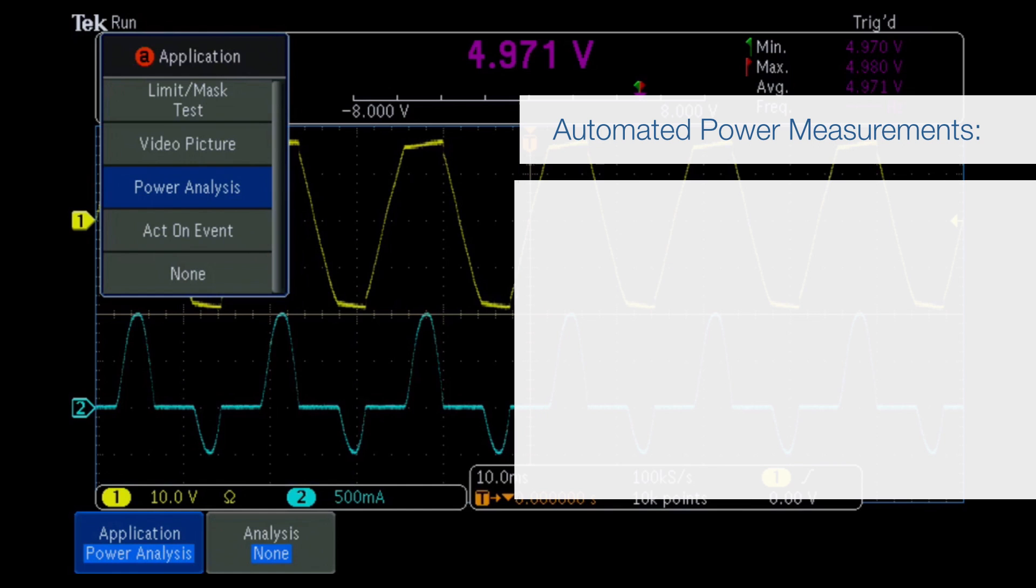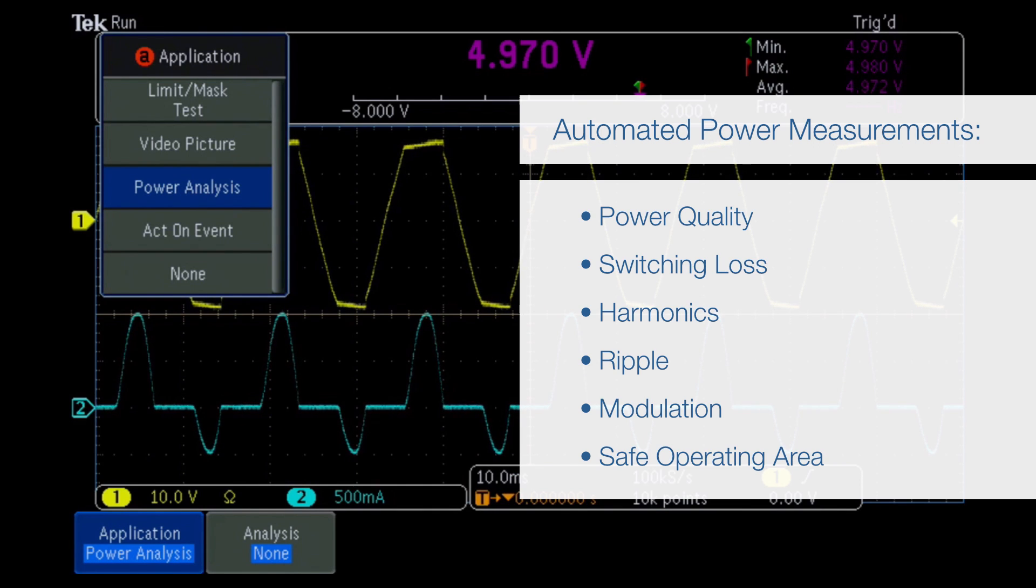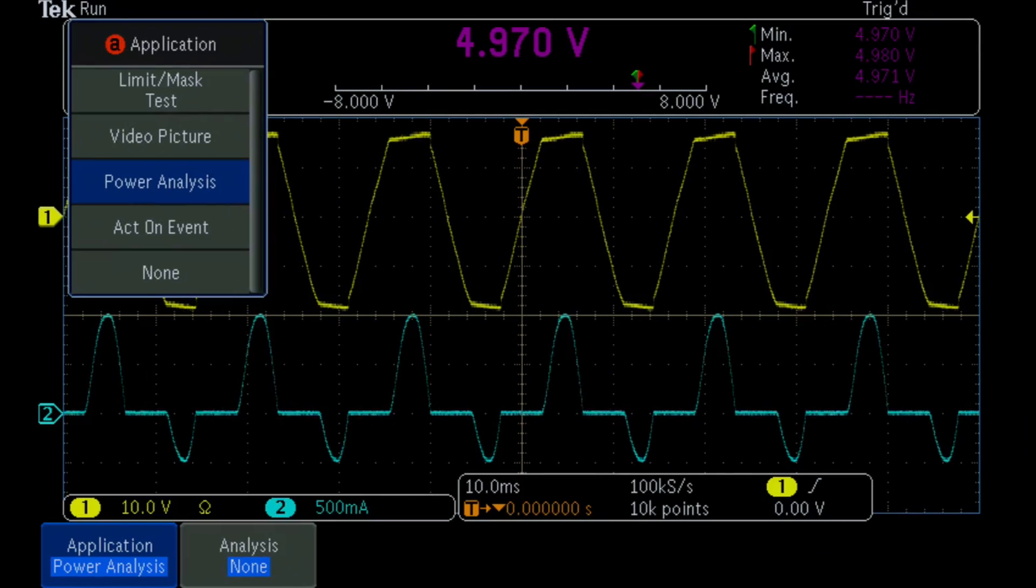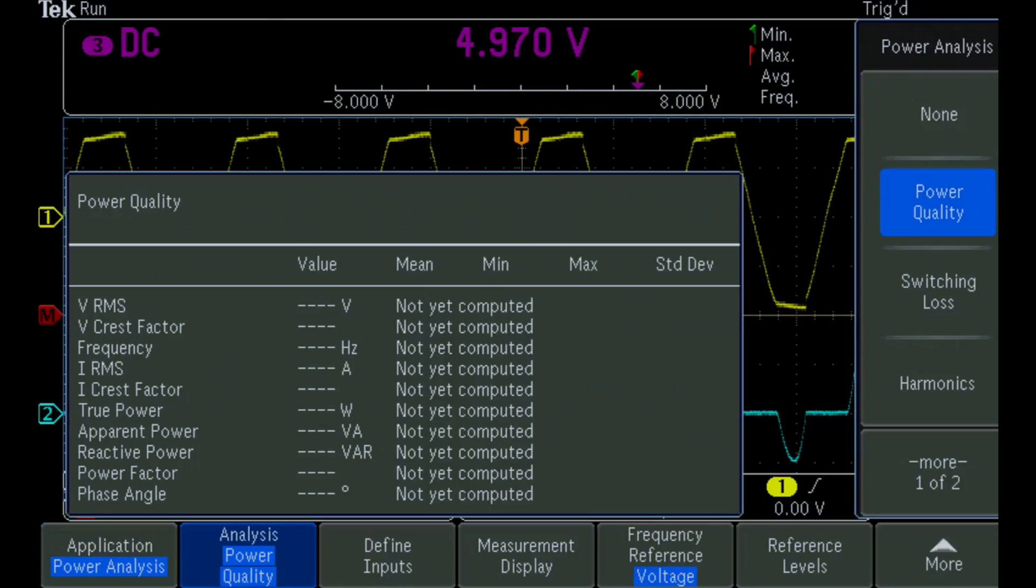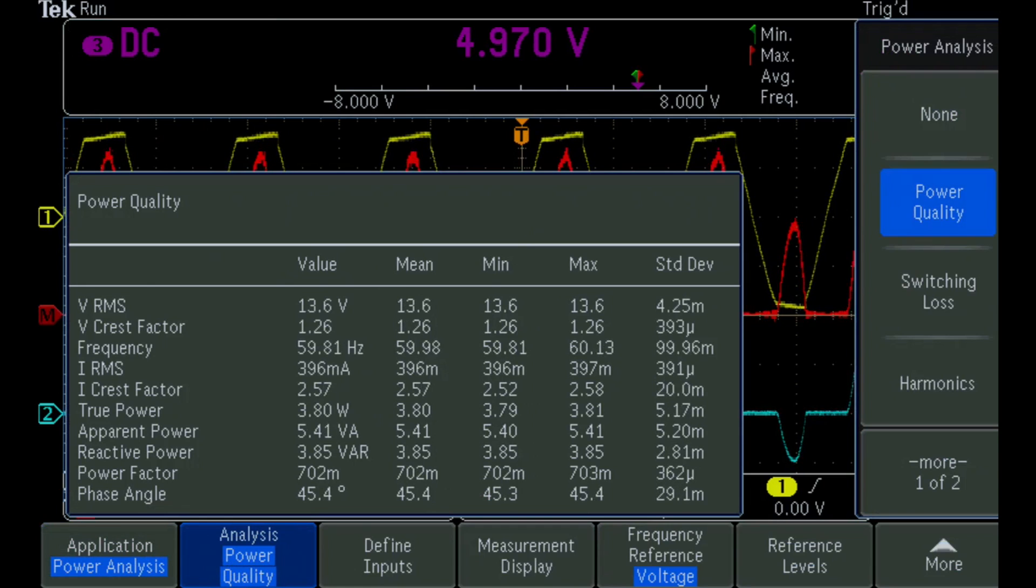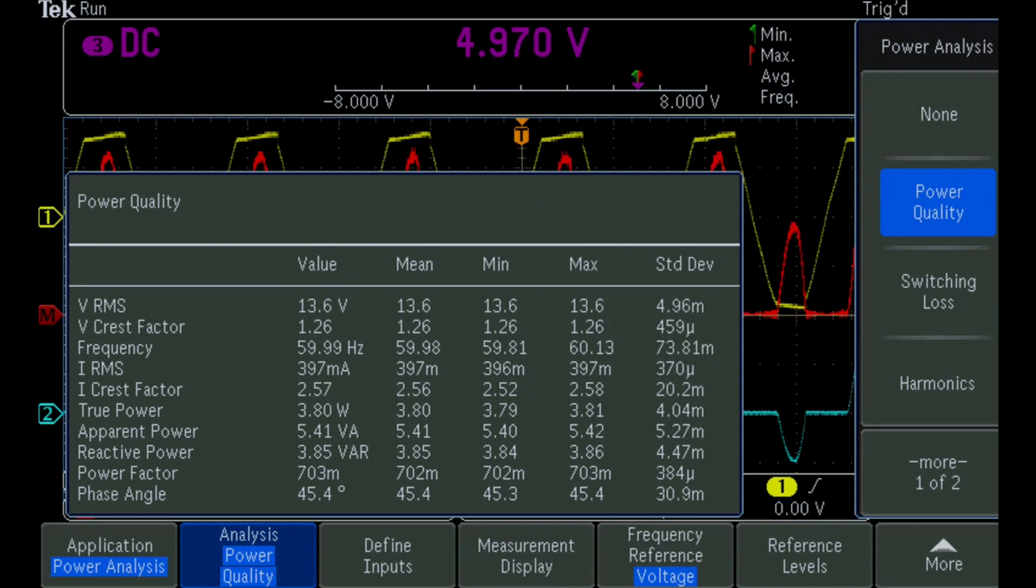The optional MDO 3000 power measurement application automatically makes a variety of measurements with the push of a button, easily and repeatably. Here are the input power quality measurements, including power, crest factor, and power factor, which characterize the effects of the power supply on the AC power source.